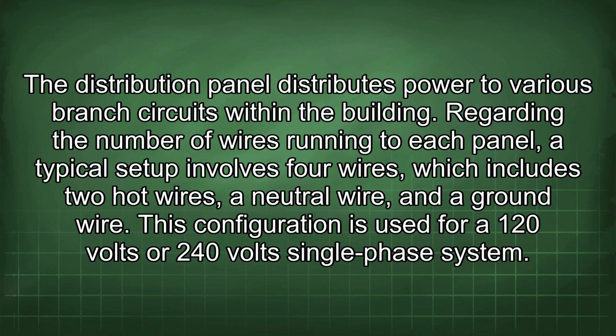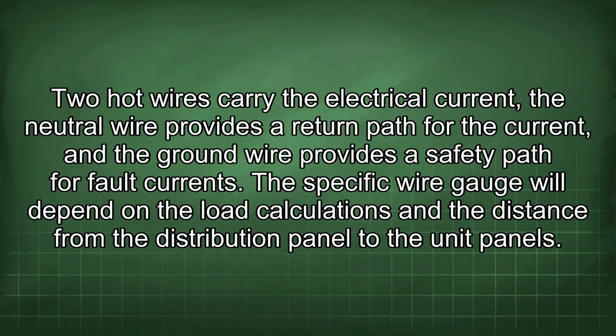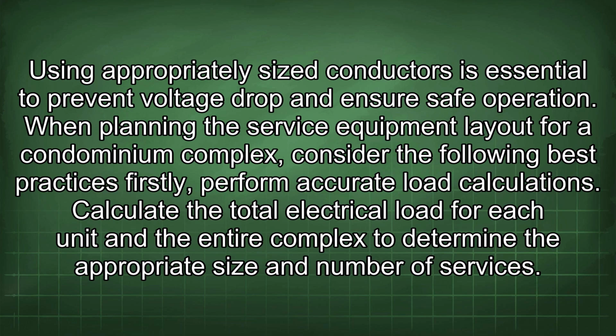Regarding the number of wires running to each panel, a typical setup involves 4 wires, which includes 2 hot wires, a neutral wire, and a ground wire. This configuration is used for a 120 volts or 240 volt single-phase system. 2 hot wires carry the electrical current, the neutral wire provides a return path for the current, and the ground wire provides a safety path for fault currents. The specific wire gauge will depend on the load calculations and the distance from the distribution panel to the unit panels. Using appropriately sized conductors is essential to prevent voltage drop and ensure safe operation.